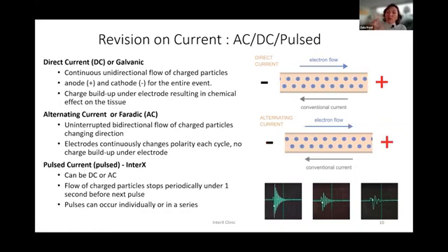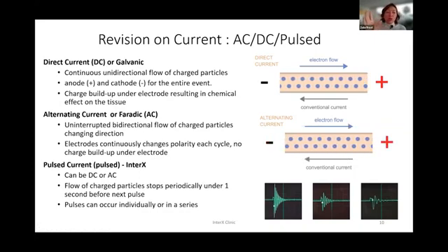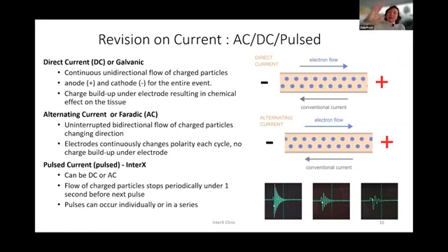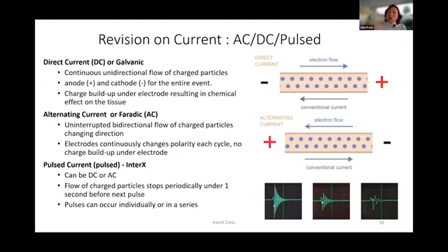Why? Because with highly conductive tissues, we don't want to overstimulate them. So it adjusts dynamically to give sufficient stimulation, but not overwhelm, so the nerve endings are still intact and not damaged by the stimulus.